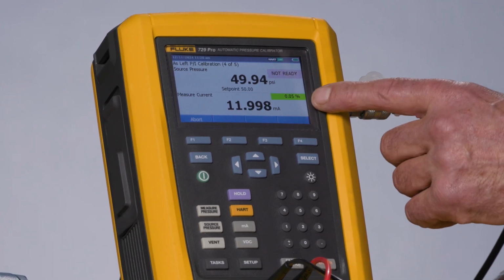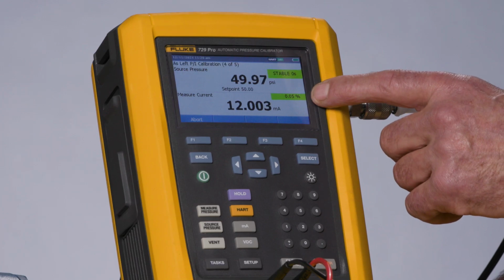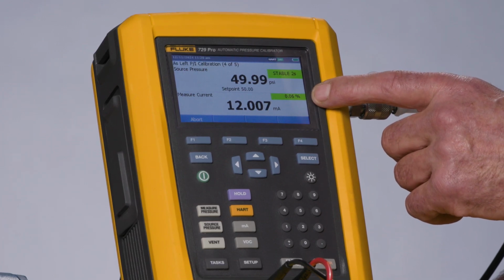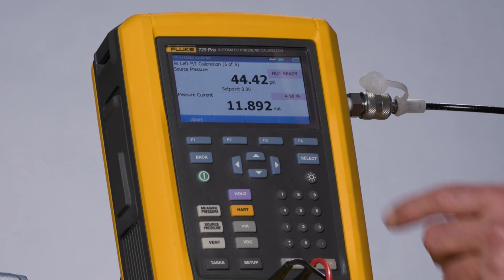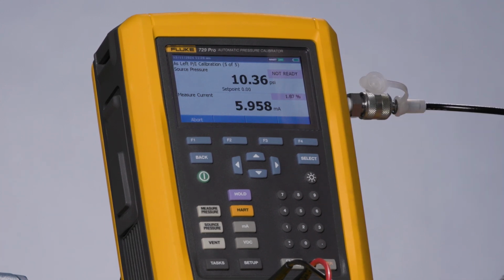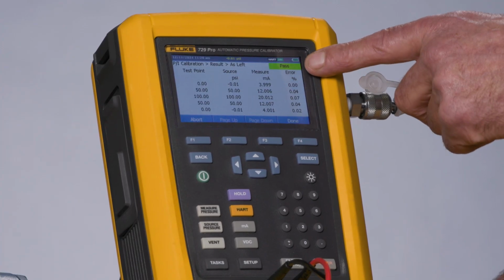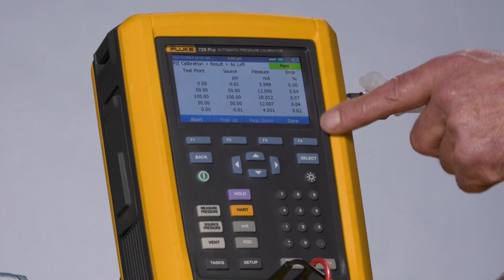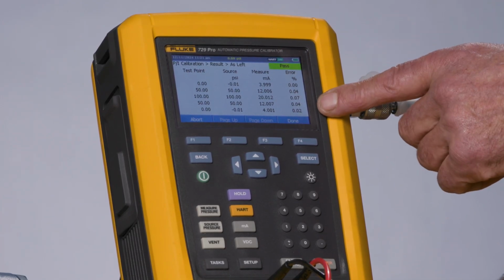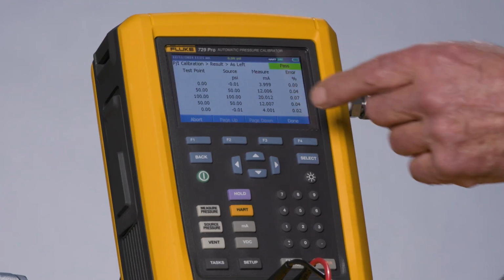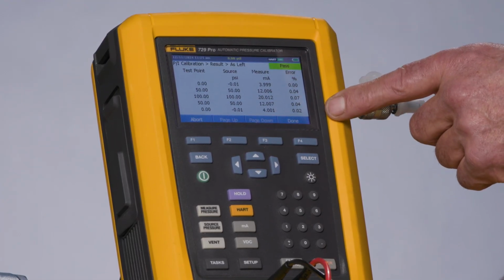Now measuring 12 milliamps, and you can see this is also in tolerance. And now to 0 psi to document the final test point. Notice now it says pass in green and none of the errors are showing in red. So this indicates that the adjustment was successful and we have adjusted out the errors of this Rosemount transmitter as documented in this as-left test.